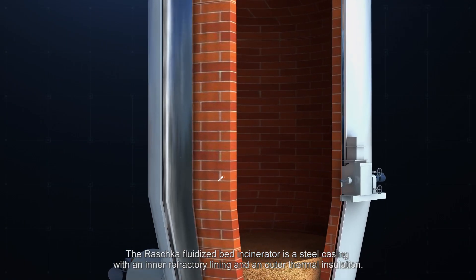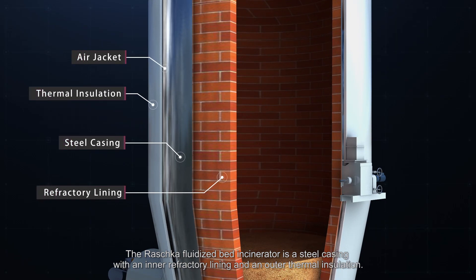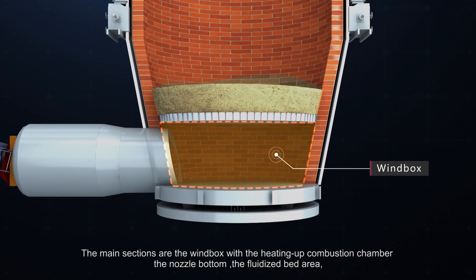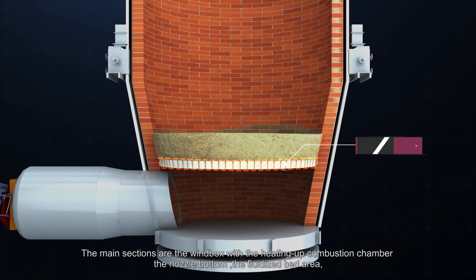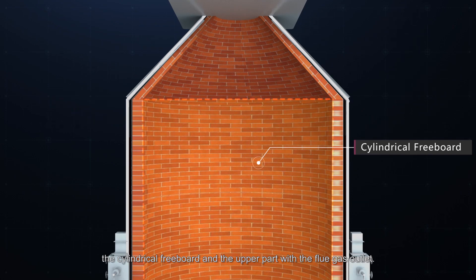The Raschka fluidized bed incinerator is a steel casing with an inner refractory lining and an outer thermal insulation. The main sections are the windbox with the heating up combustion chamber, the nozzle bottom, the fluidized bed area, the cylindrical freeboard and the upper part with the flue gas outlet.